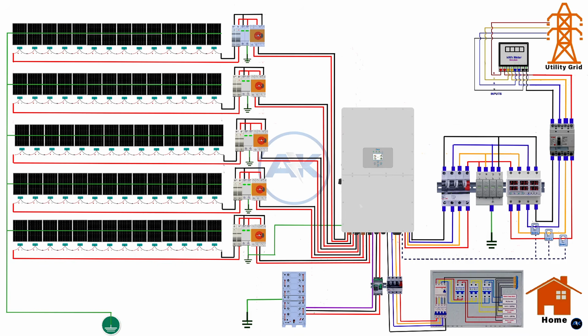Now, ground the DC side components. Connect the DC combiner box grounding terminal to the grounding bar. Make sure the DC surge protection device is also connected to the same grounding point with a short and thick earth conductor. After that, ground the AC side components. Connect the AC surge protection device, AC isolator enclosure, distribution boards, and any metal enclosures to the grounding bar.